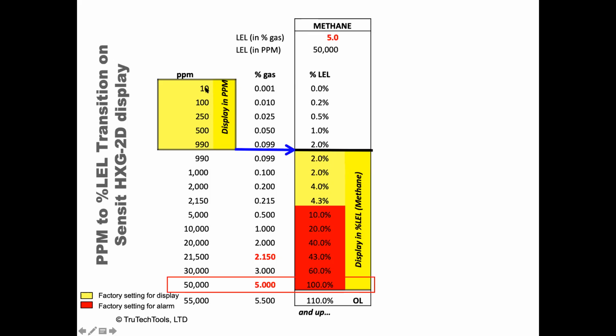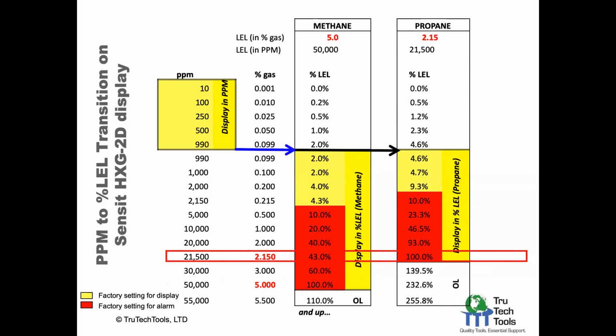So this is what you're going to see, the yellow band, the box here. It's going to transition from ppm, then it will cut over to display LEL when it's important to know that value. And one other thing, 100% LEL is 5% gas or 50,000 ppm. You never want to be there, but that's the mathematics of what's happening.